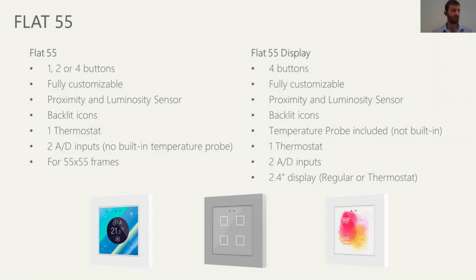There's a reason for that. The device doesn't have a built-in temperature probe because it goes into a 55 by 55 frame. So that's a standard frame. And if you left the temperature probe built in the device, you could have very wrong temperature measurements because that would be enclosed behind the frame. And that's why we didn't include it in the flat 55 nor the flat 55 display. And just because it makes more sense to use the thermostat with the flat 55 display, when ordering a flat 55 display, we include the temperature probe in it. Again, not built in. It comes with something like a 1.2 meter cable, so we've got quite a decent cable to wire that temperature probe.